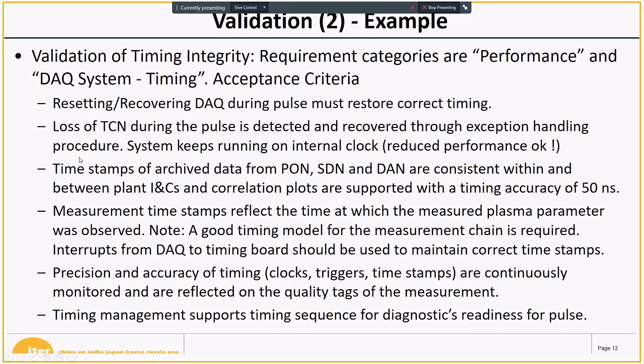Validation example for timing integrity could be, I like the timing example because many people have not spent too much effort on it. The main requirement categories for timing are performance and a DAQ system in our breakdown, the timing aspect. And acceptance criteria could be that if I have a long pulse, 500 seconds or longer, and I have an option that in case of problem with my data acquisition, I can reset it, recover it, or maybe stop it, that after this action, the correct timing is reestablished in terms of clocks, triggers, and timestamps and time.